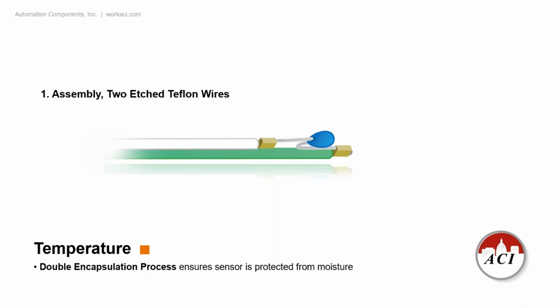So here's how we actually assemble the probe thermistors and RTDs. When we first started ACI, I remember in the back actually hand soldering these leads onto the lead wires. And a lot of times, you have to have an 800-degree tip, and not knowing to us, the thermistors were only rated up to about 400 degrees. So we would damage a lot of sensors, and a lot of times we wouldn't catch it until it was in the field. So we had a bit of a learning curve in the earlier years at ACI. We have since, what we think, perfected it, and how we feel that we are better than the others in the marketplace is we actually crimp that on there now.